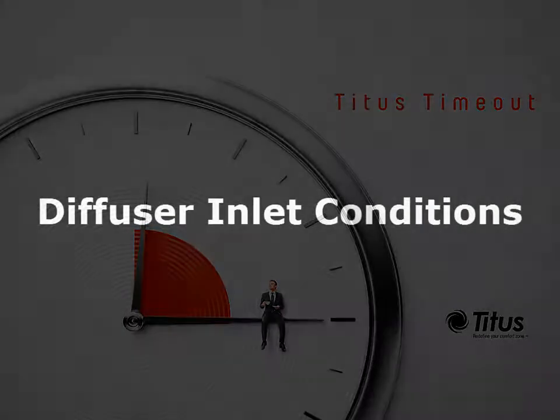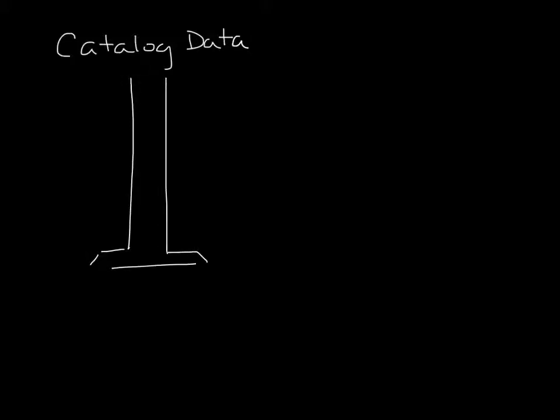I'm Jenny Abney-Civy, and today we're going to discuss how diffuser inlet conditions affect performance, especially sound. Diffuser catalog data are based on ASHRAE test standards that require 10 equivalent duct diameters into the inlet. This is great for getting repeatable data that could be compared between manufacturers, but not very realistic. I mean, when was the last time you had 10 equivalent duct diameters in a ceiling plenum?